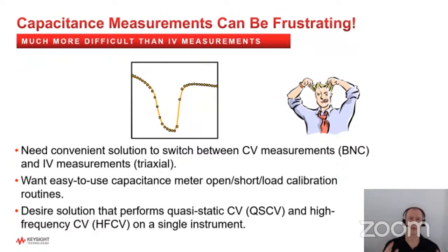You also, when you do a capacitance measurement, you have to do a lot more calibration. You have to do, at a minimum, open short. I'll talk about that later. Open short, and also load calibration. So having an easy way to do that is important. And also, as I'll mention later, I'll talk about quasi-static and high frequency. You really need a solution that can do both easily, because you actually need to do both types of CV measurement to get complete data on a semiconductor device.